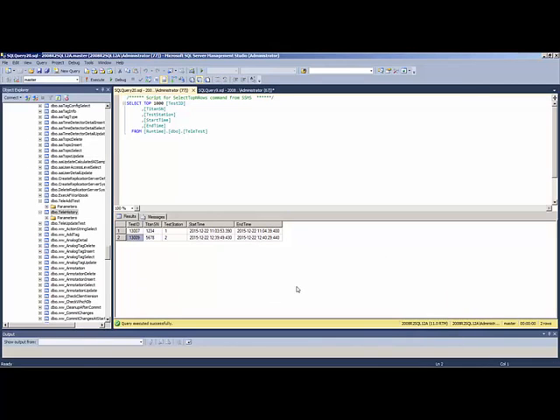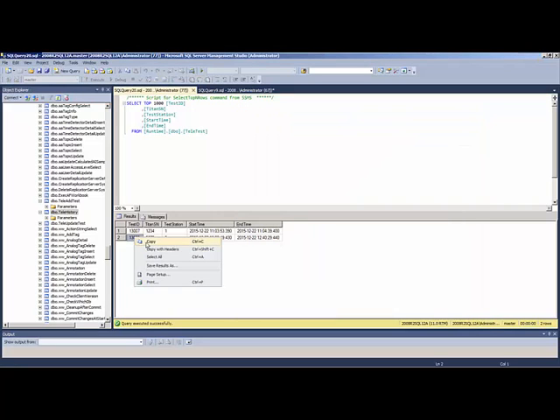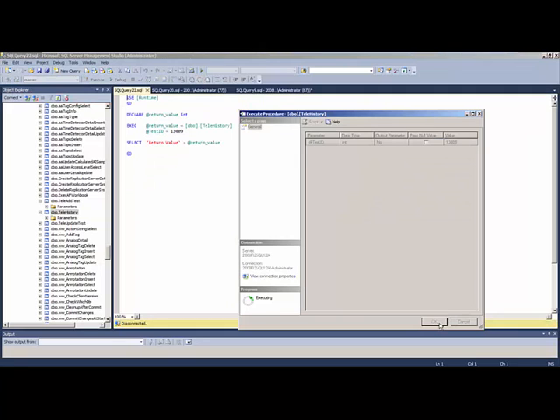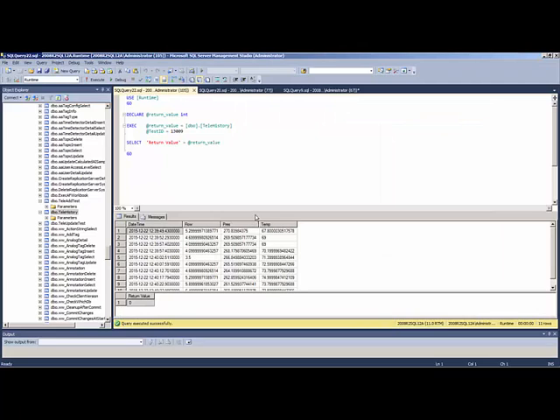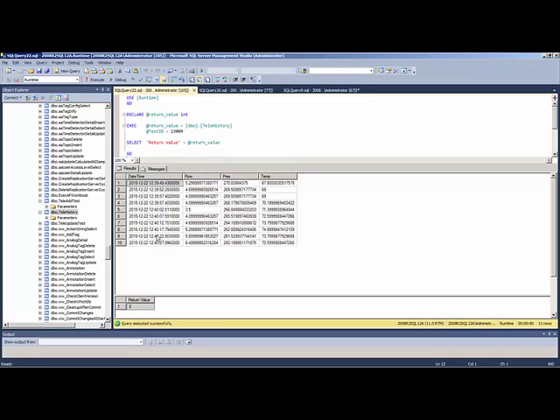Now we're going to take a look at how we query that data from the Wonderware Historian using the information stored in this table — the test ID, serial number, test station, start and end time. We have a stored procedure that we're going to execute. I'm going to pass in the test ID into that stored procedure. Executing it — there's the result set that got returned. We're pulling that information from the Wonderware Historian, correlated to the time the actual test was taking place — here's the flow, here's the pressure, and here's the temperature.